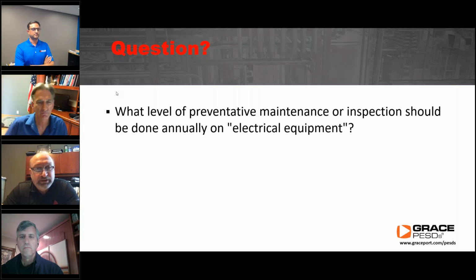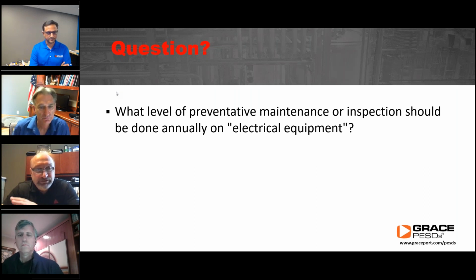In Z463 for Canada, we explicitly said we want the priority to be on safety, then reliability and criticality of service. But the old adage is, if you do more maintenance, you're going to have better reliability and probably a lower likelihood of fault conditions. Some companies also have insurance implications to consider, so it's not only safety and risk, but insurance issues as well that are reasons to take a closer look at the frequency.